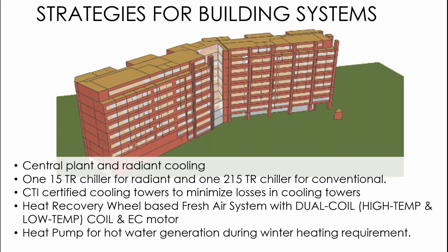Then in terms of the selection of equipment, as you can see on the slide, we have CTI certified cooling towers. Cooling tower fans are also with variable frequency drives. We are using a heat recovery based fresh air system. What does it do? When we talk about raw fresh air at 43 degrees Celsius, I have to cool it down to 24 degrees Celsius to supply inside a room. But what the heat recovery wheel does is it takes the exhaust from the toilet.